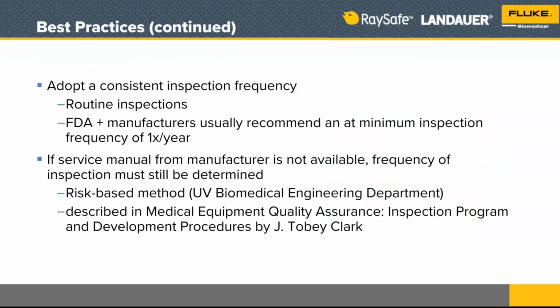You want to adopt a consistent inspection frequency. We said once per year, that's what's generally accepted. But you can make a different choice. I'm going to show you one way that you might be able to either cross-check the manufacturer's inspection frequency or come up with one of your own that matches better with the failure rates that you're seeing in infant incubators in your own inventory.